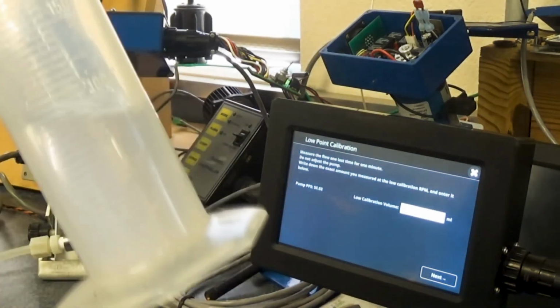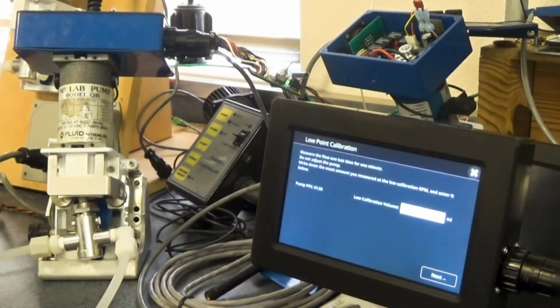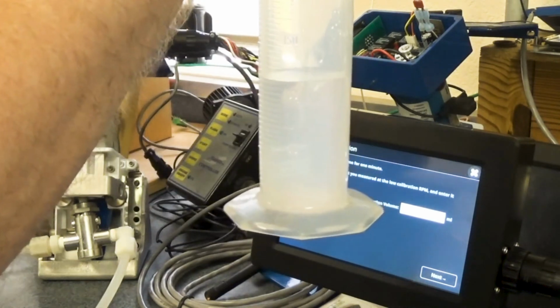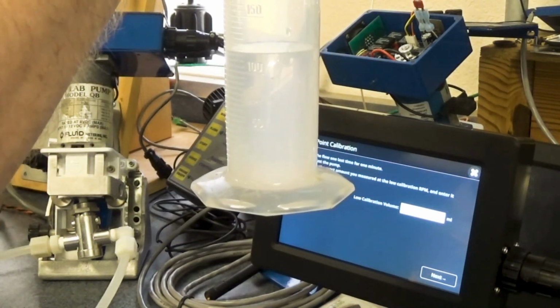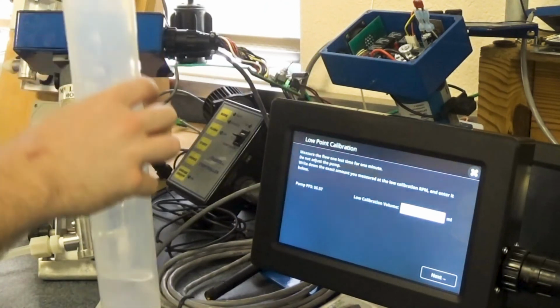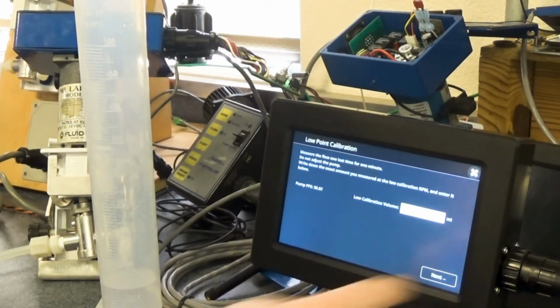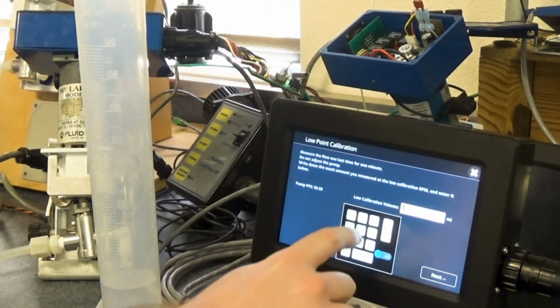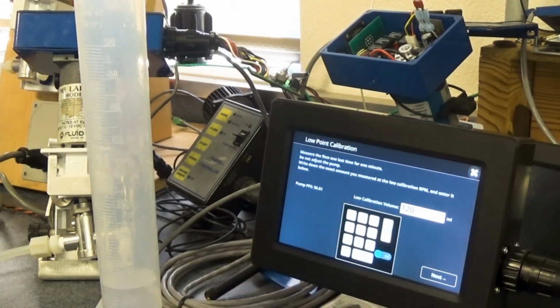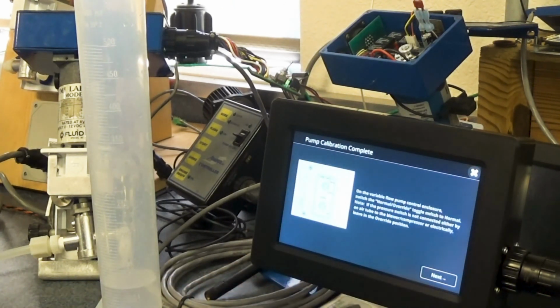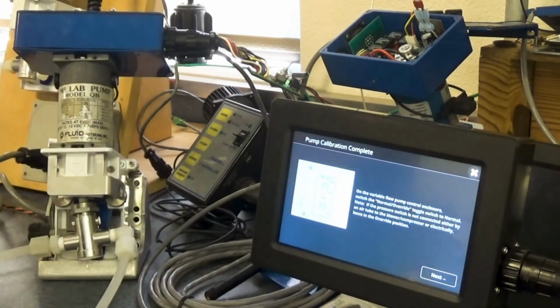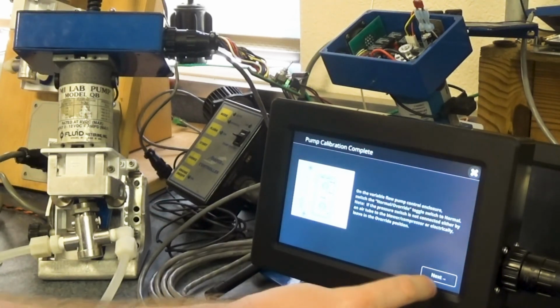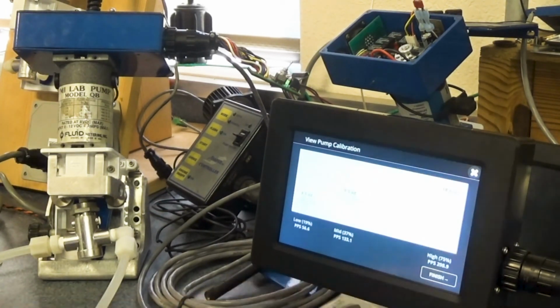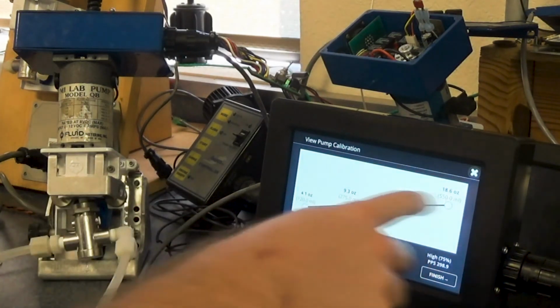A minute has passed, and it looks like we got about 120. So we'll type in 120 milliliters, and you'll hear that the pump has stopped. What it's indicating right here is to make sure that you put your switches back to where you found them before you started calibrating. And if you press next one more time here, we should see a linear slope.